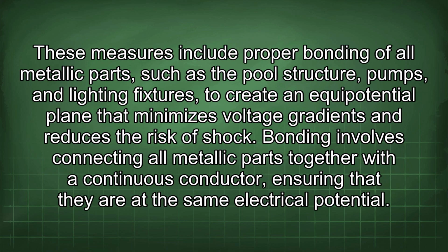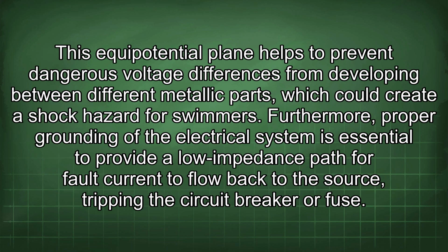These measures include proper bonding of all metallic parts, such as the pool structure, pumps, and lighting fixtures, to create an equipotential plane that minimizes voltage gradients and reduces the risk of shock. Bonding involves connecting all metallic parts together with a continuous conductor, ensuring that they are at the same electrical potential. This equipotential plane helps to prevent dangerous voltage differences from developing between different metallic parts, which could create a shock hazard for swimmers. Furthermore, proper grounding of the electrical system is essential to provide a low impedance path for fault current to flow back to the source, tripping the circuit breaker or fuse.